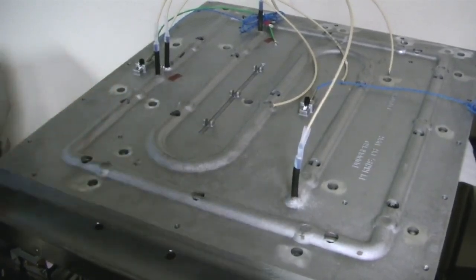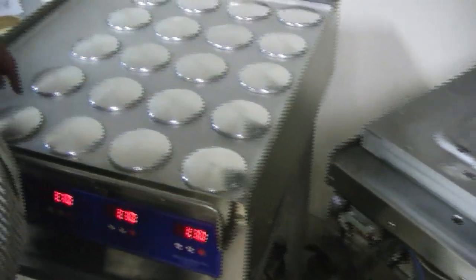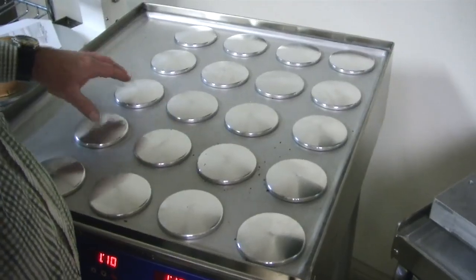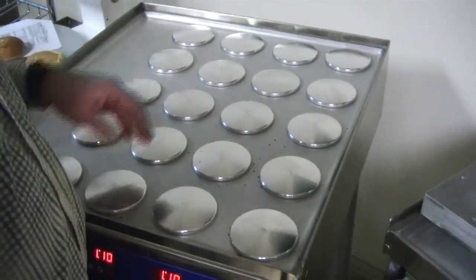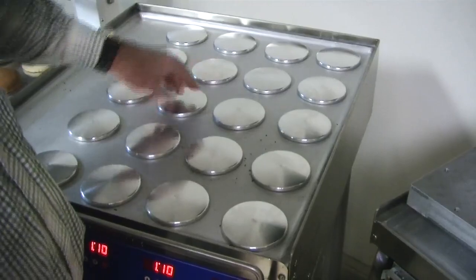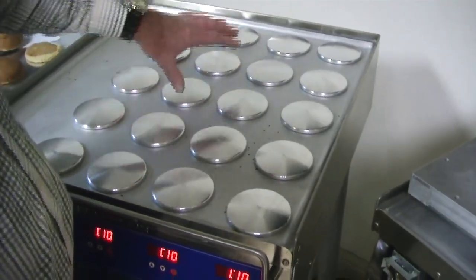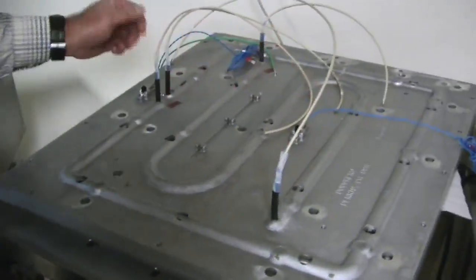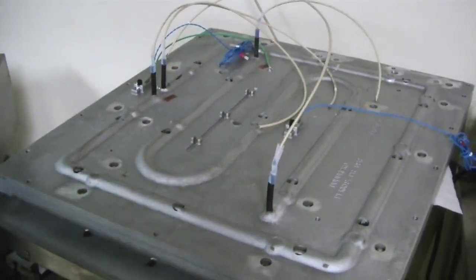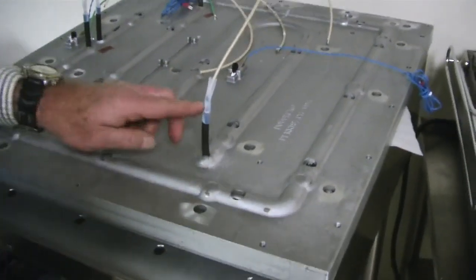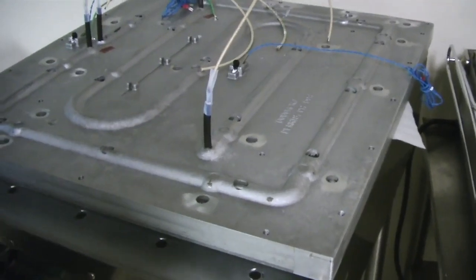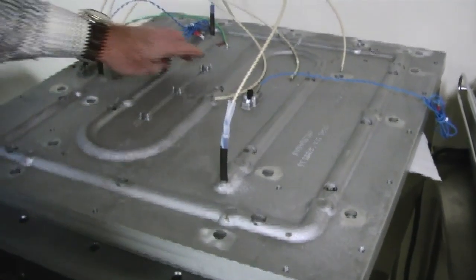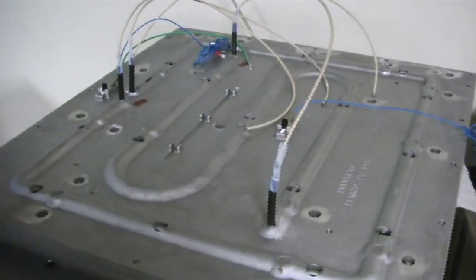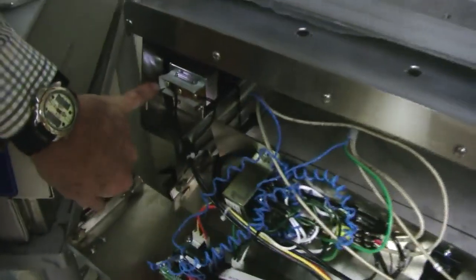The outer perimeter is meant to control the heat from the outer area, because it cools quicker than the center. The center one controls the temperature in the center areas. It's followed by 2 sensors for zones 1 and 2. These are RTD 2000 ohm sensors. The wire is brazed on, and that's how we do it here. We silver braze the wiring on, about as good a connection as you could possibly have. And this spot here is for the high temp limiter, which sits right here inside the grill.